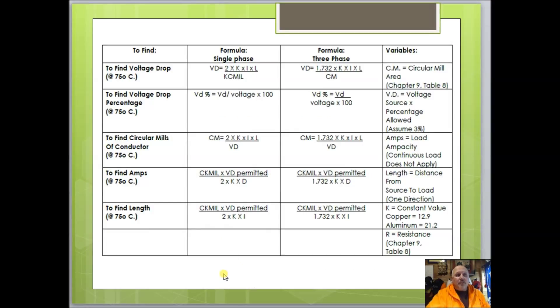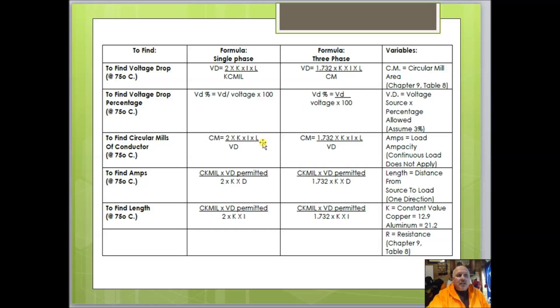For the formulas: to find voltage drop for single phase, it's VD = 2 × K × I × L ÷ circular mills. For three phase, we only change the 2 to 1.732 — the rest of the formula stays the same. To find the circular mills (size of wire), it's CM = 2 × K × L × I ÷ voltage drop — where voltage drop is the voltage times three percent. For three phase, again replace 2 with 1.732.